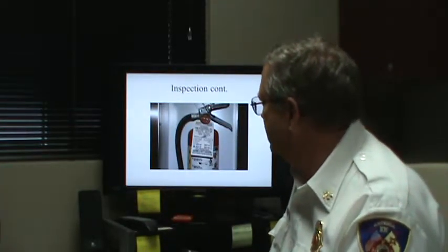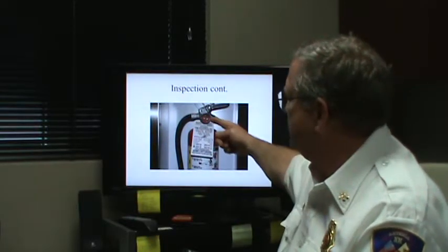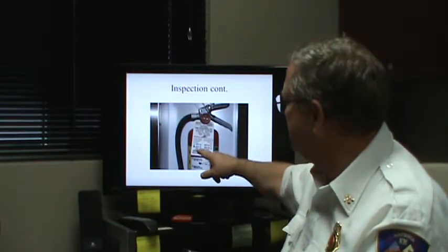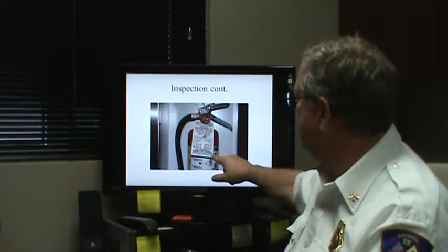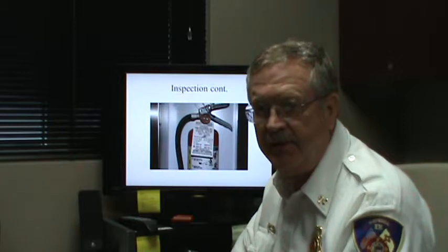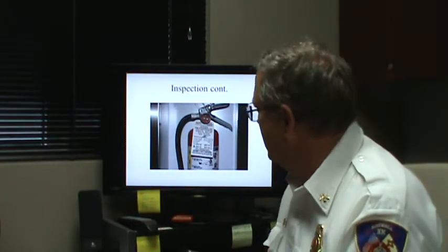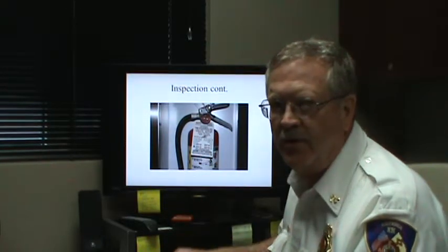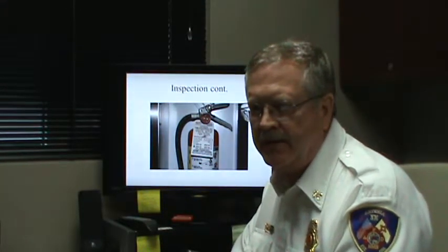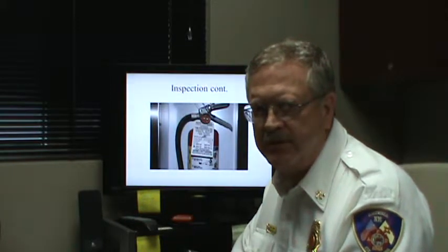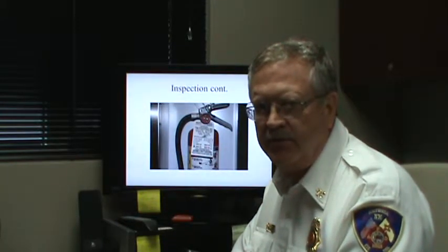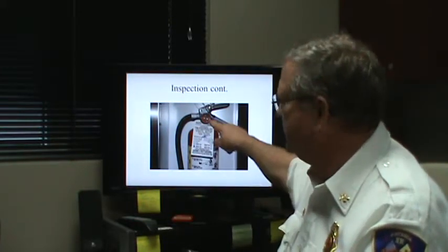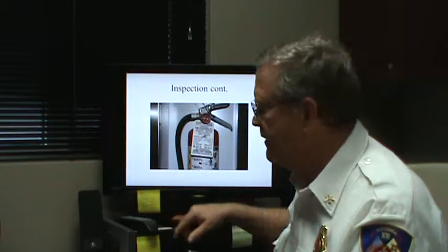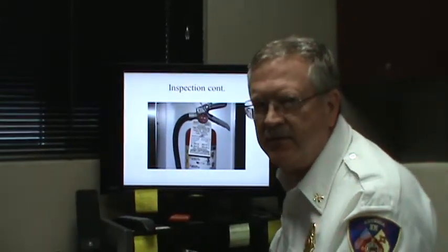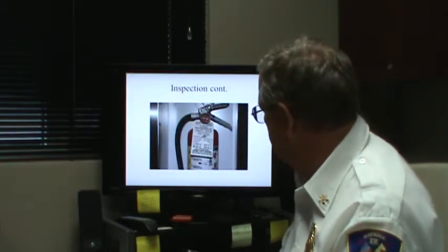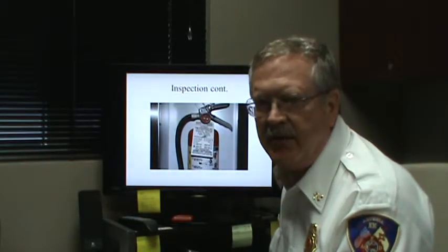Okay, there's a picture of the extinguisher. The gauge shows in the green. The tag shows that it was inspected last year in January. So in a month or so, we'll have to have them inspected again. This is inside a closet mounted on the wall, and it's mounted 4 inches off the floor at a minimum, and a maximum, I believe, of 4 foot up to this point here. This one's actually shorter than that, but it's well within the maximums of what the requirements are for fire extinguishers. All the fire extinguishers that are located in this building are ABC type.